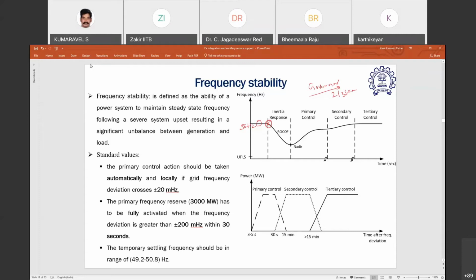Not that it can increase instantly. It will start increasing the power if it has a margin. So if it is a 100 megawatt conventional power plant which is operating at 90 megawatt, it has a 10 megawatt margin. This will typically start reacting to the frequency disturbance at 2-3 seconds from the disturbance, and then it will start increasing. Let us say it was at 90 megawatt, it has 100 megawatt capacity, the disturbance took place, and it will take 2-3 seconds to respond, and after that it will start increasing its output. That is how it will happen. But what did I say? Generation is lost instantly, in no time. 800 megawatt we lost in no time. Load is the same.